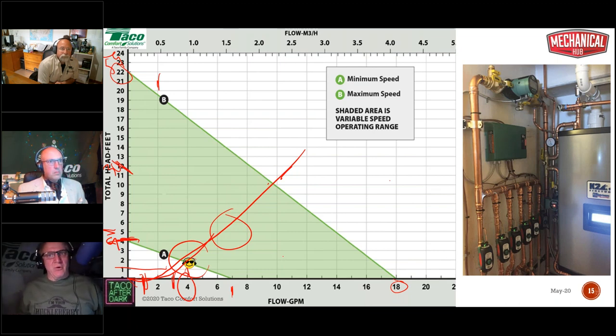As it gets warmer and warmer out, that delta T will start to shrink some. But the point here is it's not going to have a 5 degree delta T. That's the point. I don't know why people find that so hard to understand. There are some folks out there that just don't get this, but that's all we're trying to do: keep the delta T as wide as we can for as long as we can, so the boiler short cycles as little as possible. Is it going to short cycle some as we get into the warmer months? Yep, there are no two ways around that. It's just not going to be as bad as it was.